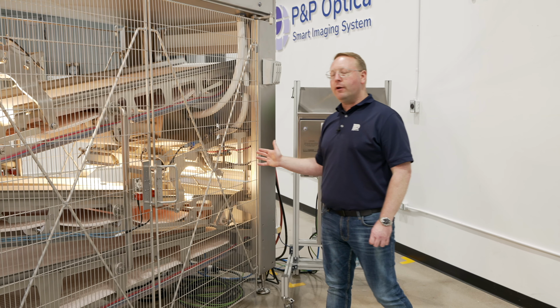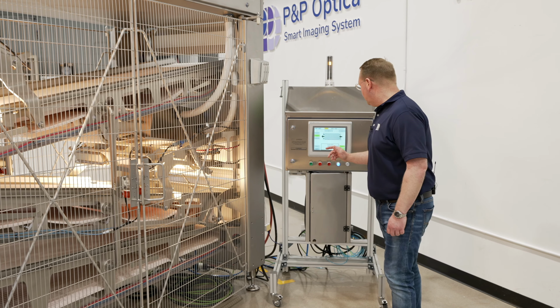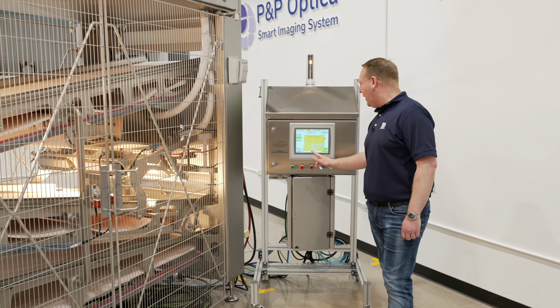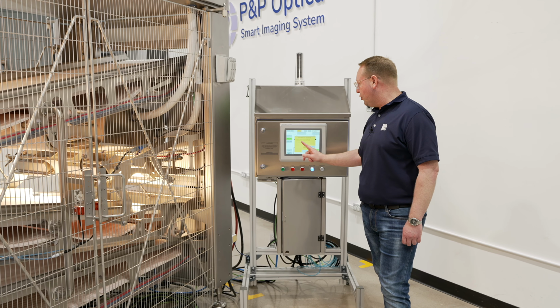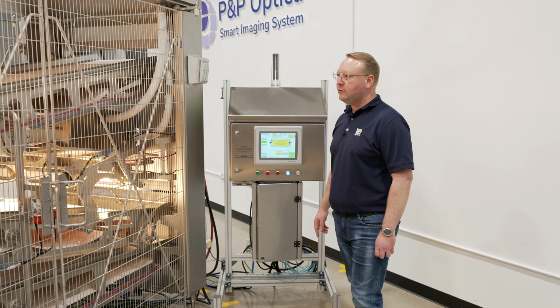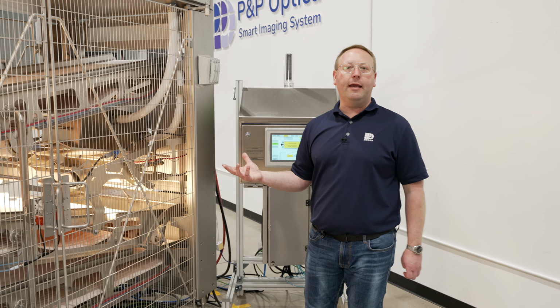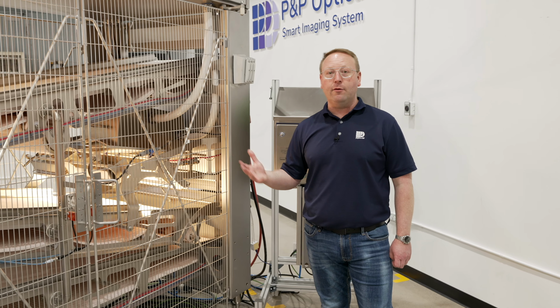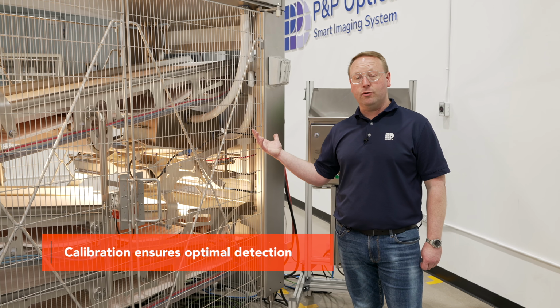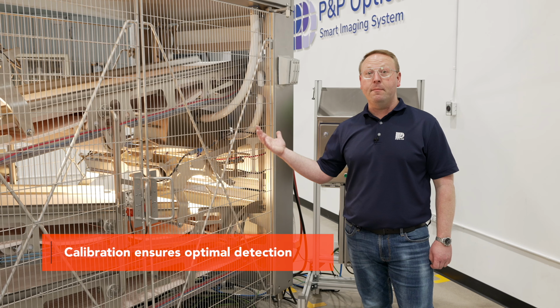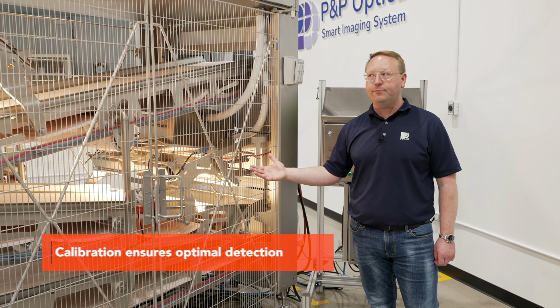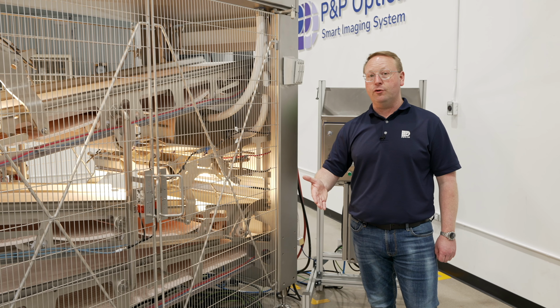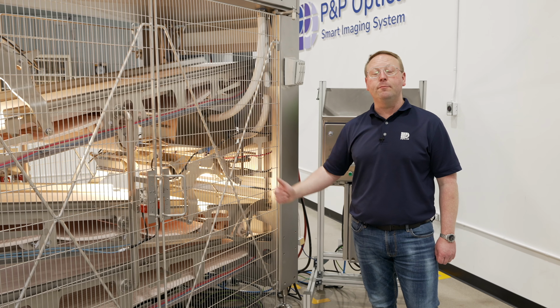So I'm going to trigger calibration now so that we can start scanning. So it asks you, sure you want to do that? You click yes. Now, the lamps need to be in a steady state before calibration can take place, where you have to wait a little bit of time, making sure that a minimum of 90 seconds has elapsed from the time the lamp's turned on to the time the calibration begins.